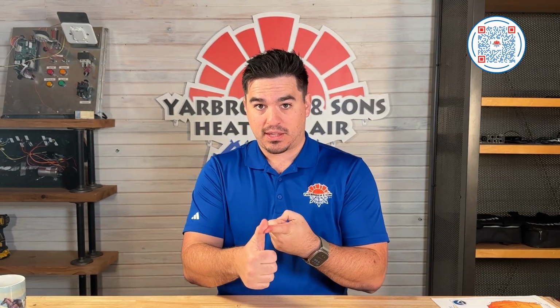So I don't want to oversize that system, because that creates more problems than whenever the system was undersized. The undersized system actually does a better job removing humidity from the home than a system that is oversized. And if the system is oversized, some symptoms you may be experiencing is high humidity within the house.